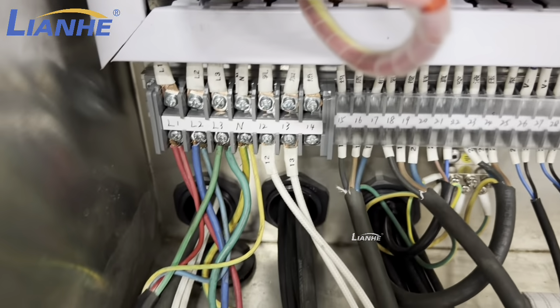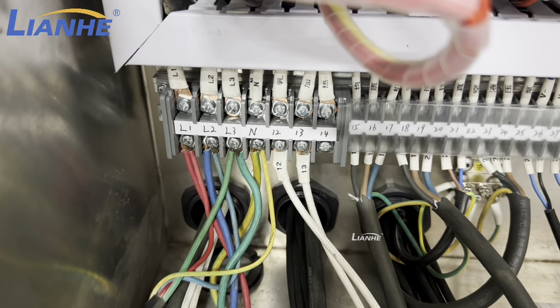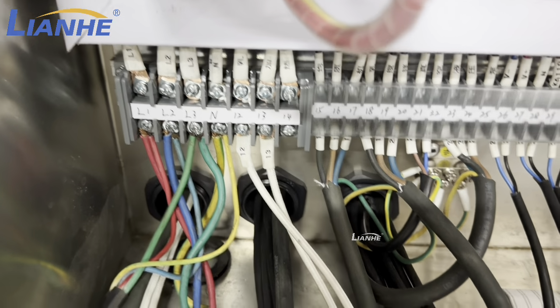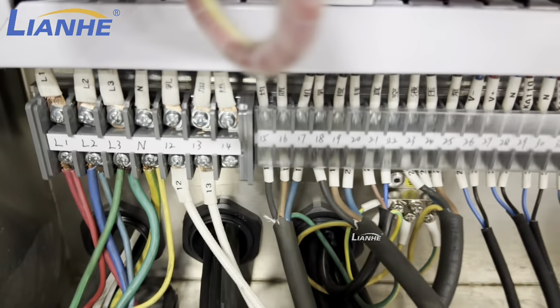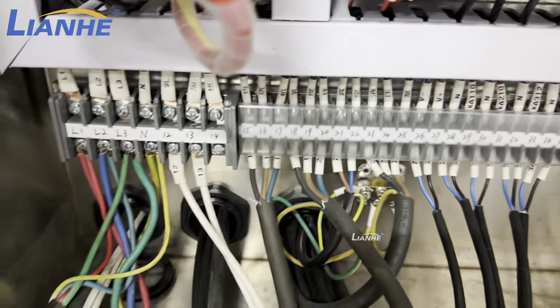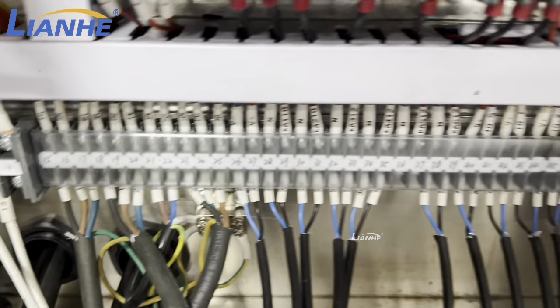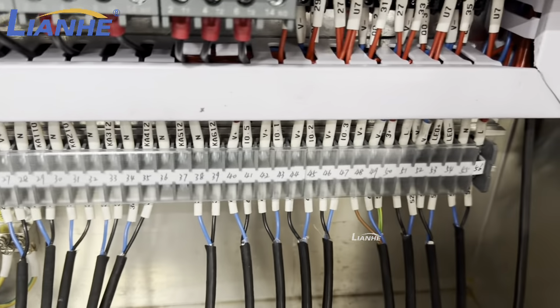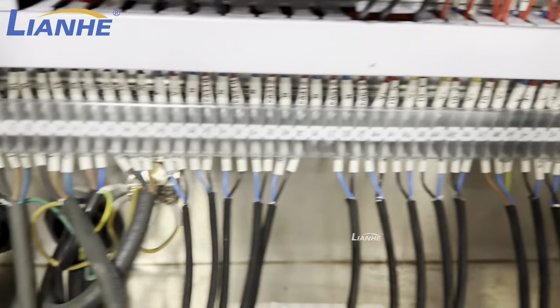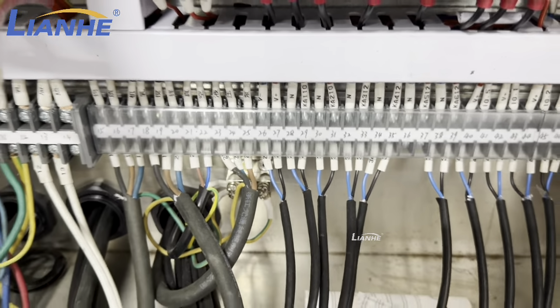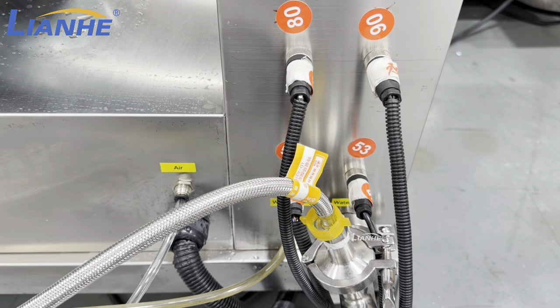And you should connect the wires here, L1, L2, L3 wire, the neutral wire. And the ground wire here, you should also connect it. And these wires, we have marked the numbers on it, so you can connect it according to the same number. And then let's check the back side.